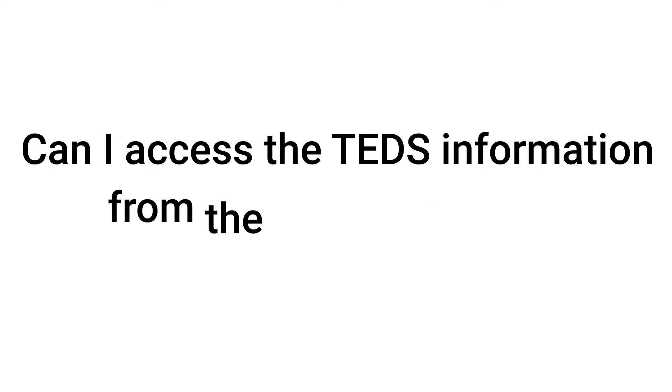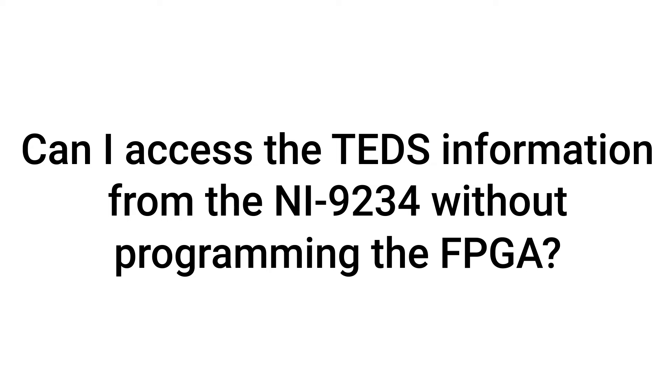Can I access the TEDS information from the NI9234 without programming the FPGA? No, you cannot access TEDS information on the NI9234 while in scan mode. The module must be in FPGA mode.